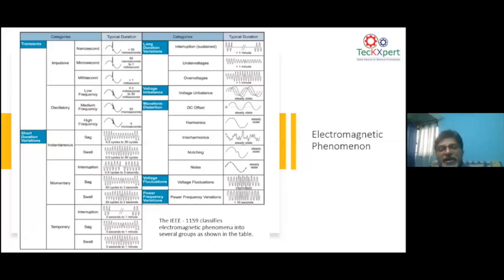And then voltage unbalance: we all know RYB, if the phases are not balanced, you have voltage unbalance. Now, waveform distortion: as you have a load connected to the voltage grid, certainly it starts drawing current, and then depending on the type of load, if it is a power electronic load, or a high frequency load, or a very dynamic load like a welding load or an arc furnace load, certainly it produces distortions in the current waveform. Power electronic devices, you all know, produce a lot of harmonics and interharmonics, and they can sometimes produce subharmonics. When I say subharmonic, it could be below the 50 cycles.